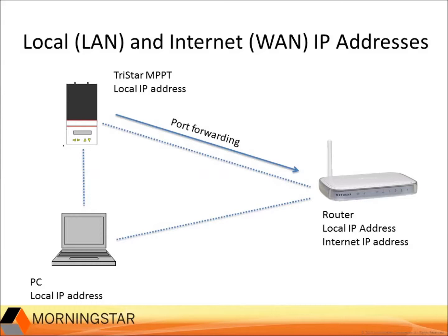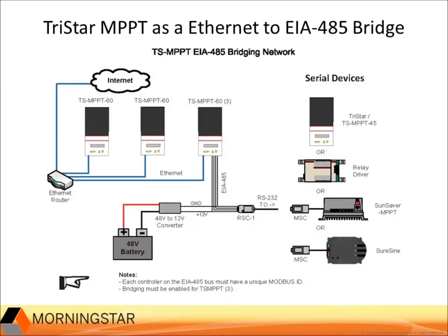Here's a simple diagram showing an Ethernet TCP/IP network configuration. The TriStar MPPT is part of the local area network, and the router is set up with port forwarding to be able to connect over the internet. In this final networking example, the TriStar MPPT-60 provides an Ethernet TCP/IP link or bridge to an EIA-485 network. This makes it possible to assign an IP address to the serial devices so they can connect to the local area network and the internet.